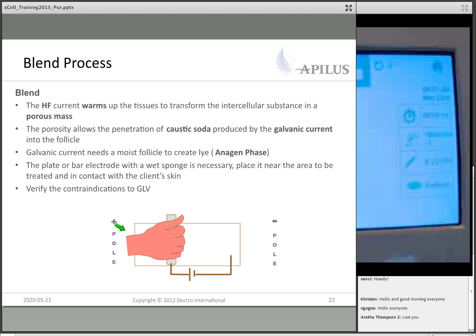The blend uses both high frequency and galvanic current. High frequency is the thermolysis we were just going through. And the high frequency in the blends, for the most part, is just there to prepare the follicle, the same way that we had it in Multiplex, where it's prepping the follicle, it's increasing conductivity. But instead of prepping the follicle for pulse of thermolysis, it's prepping the follicle for the galvanic current. So the high frequency warms up the tissues and transforms the intercellular substance into a porous mass. The porosity allows the penetration of the caustic soda that is produced by the galvanic current in the follicle.